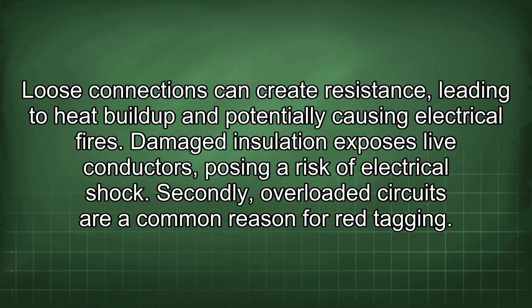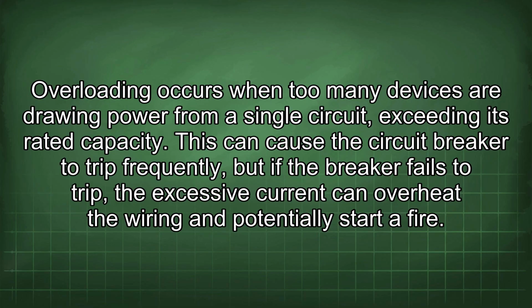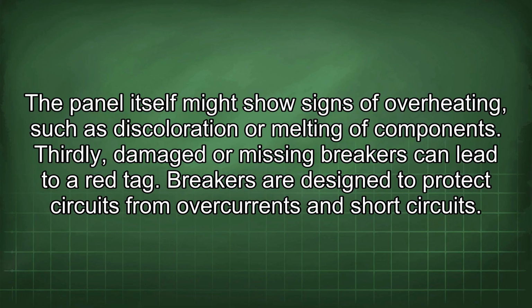Secondly, overloaded circuits are a common reason for red tagging. Overloading occurs when too many devices are drawing power from a single circuit, exceeding its rated capacity. This can cause the circuit breaker to trip frequently, but if the breaker fails to trip, the excessive current can overheat the wiring and potentially start a fire. The panel itself might show signs of overheating, such as discoloration or melting of components.